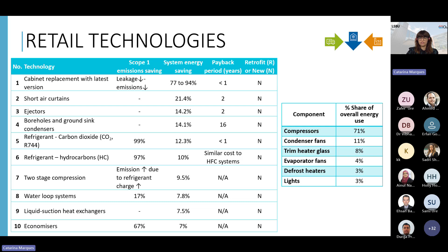For retail, the biggest intervention is actually replacing the cabinets with the best available on the market. Right now, the best is a cabinet rated B. But there are other technologies: short air curtains, ejectors, boreholes, and looking at low GWP refrigerants. There are all these options. And the cabinets that are the best ones available on the market all have doors, which definitely reduces infiltration and reduces energy.